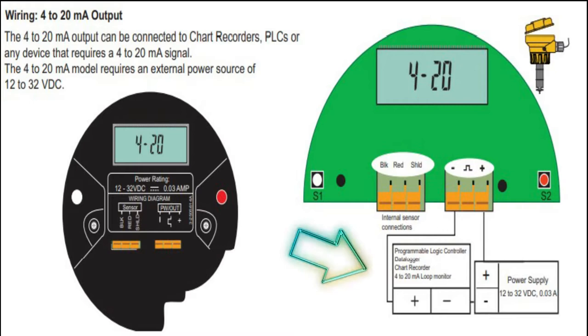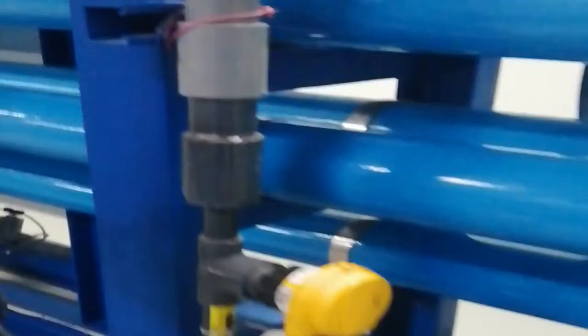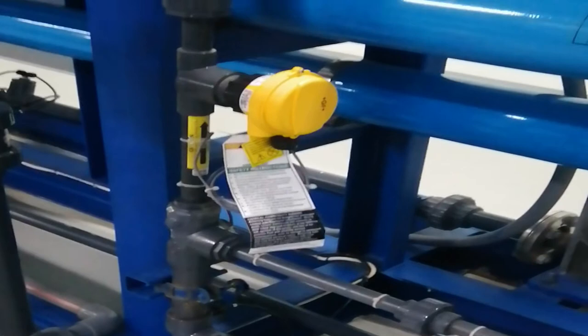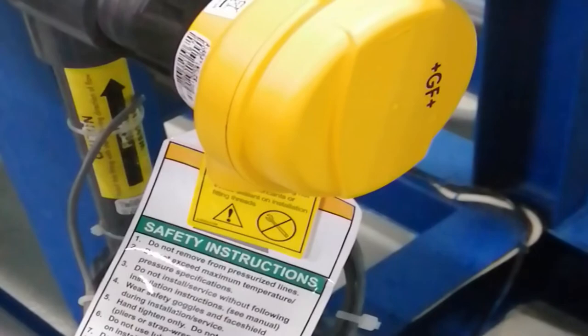The wiring of the flow sensor is looped to power supply and PLC. Flow sensor power is present. 4 to 20 milliamp is displayed in the sensor monitor, meaning the wiring is good and we have to check the sensor itself.